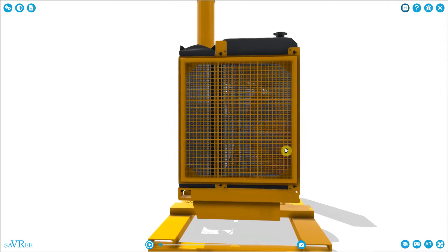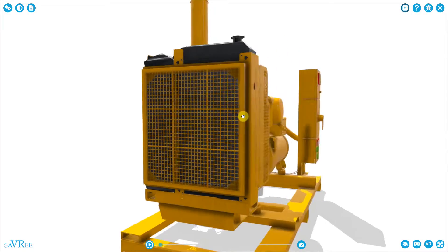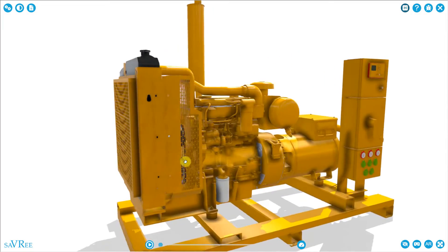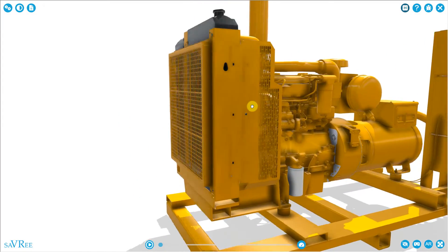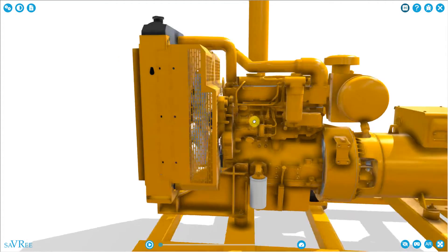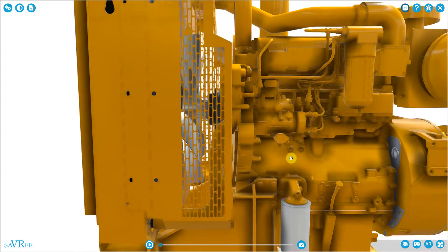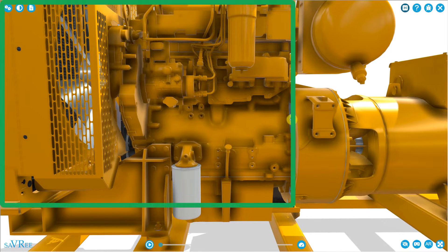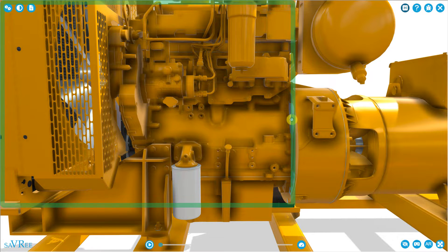A quick and easy way to do it is to install one of these electrical generators, or if you need redundancy, you install more than one. Let's have a quick look at what this generator is and how it works. We're using air for cooling — that's what this front section here is for. We blow air across a heat exchanger. We've got an engine to the left, and it's this reciprocating internal combustion engine — RICE — that we're going to use as a prime mover to generate electrical power.